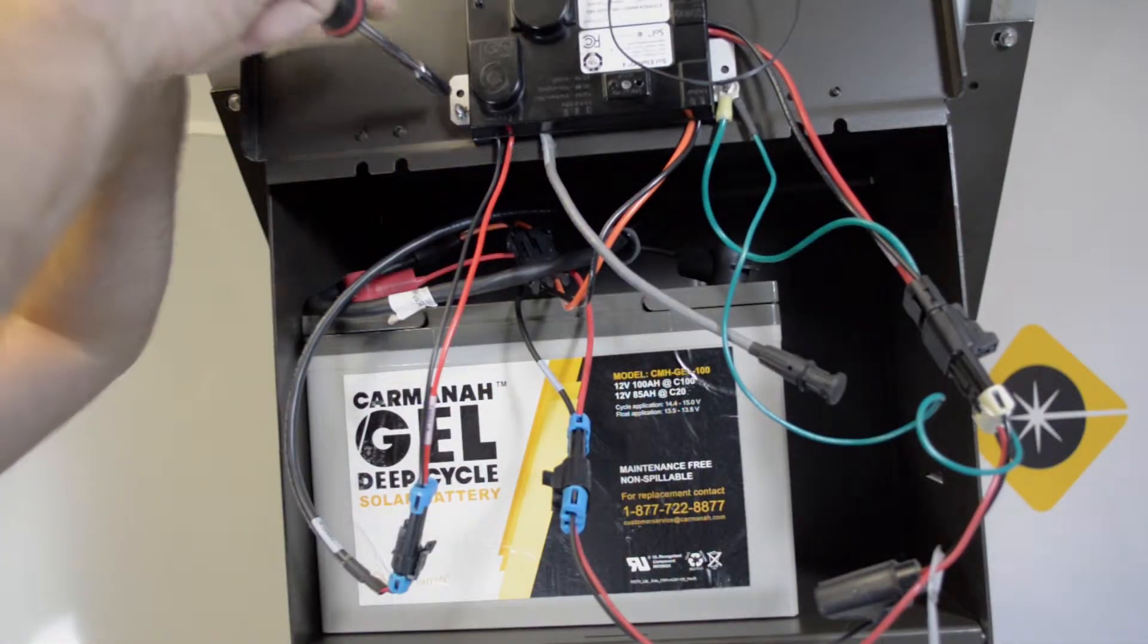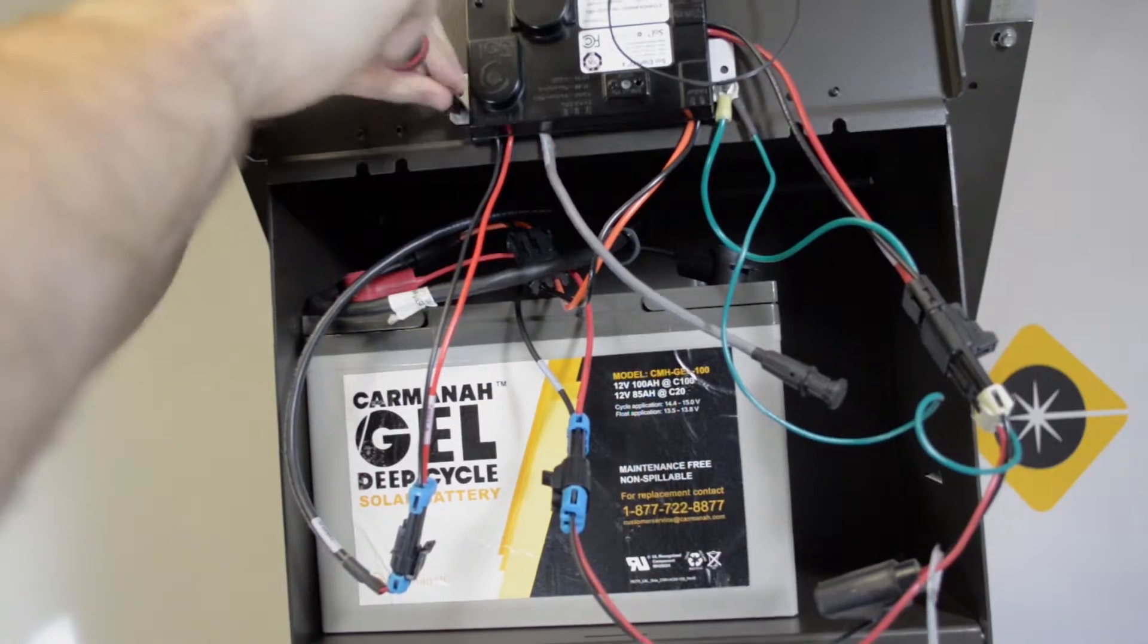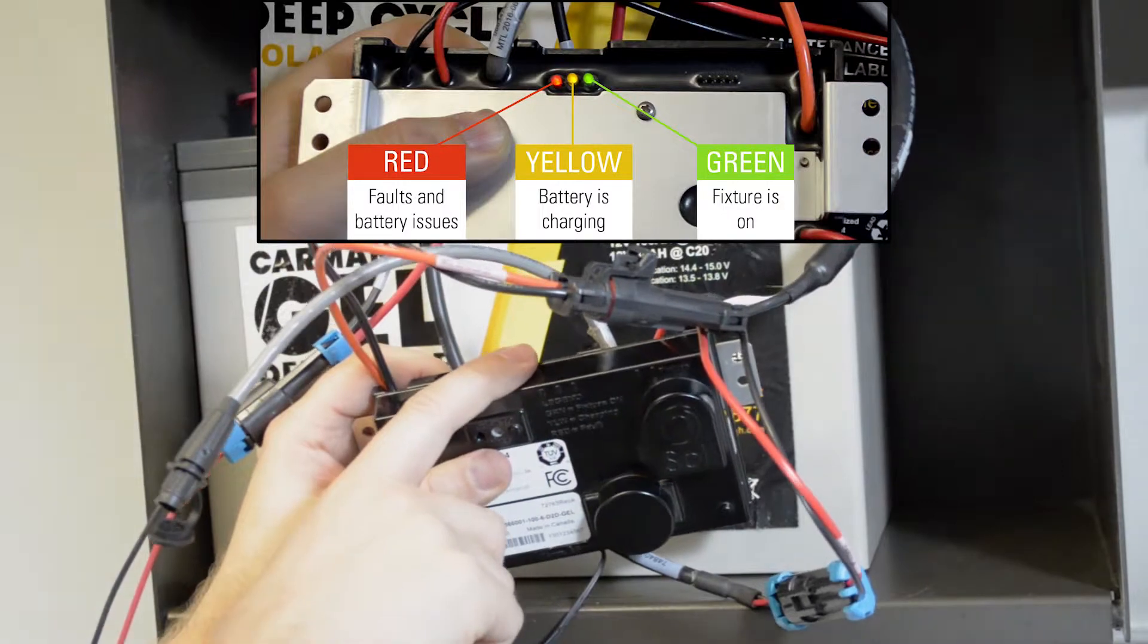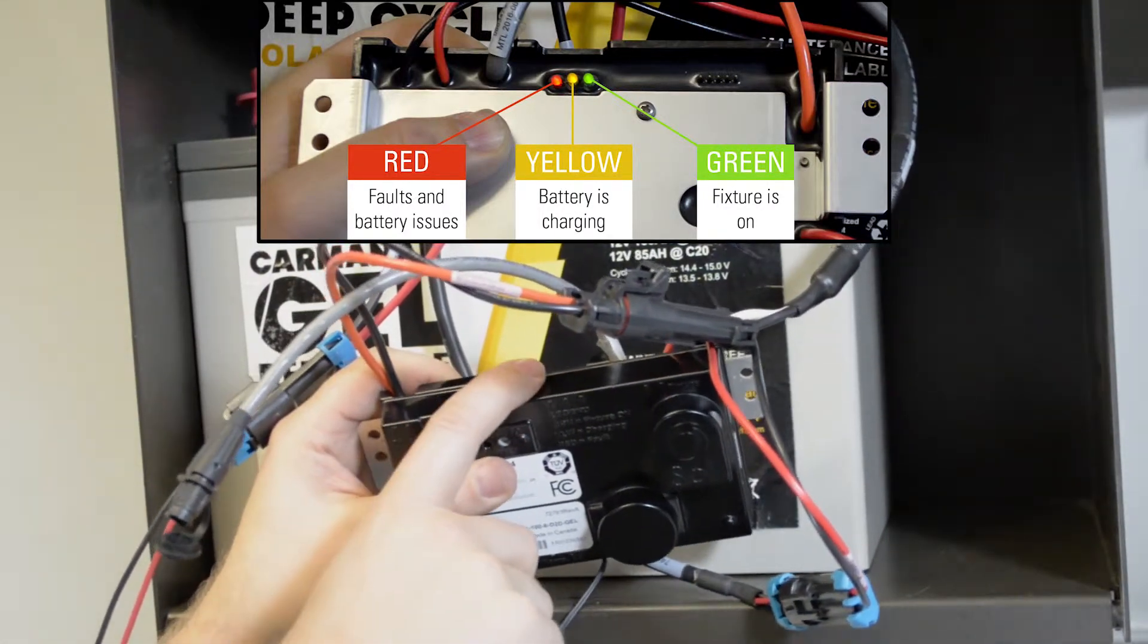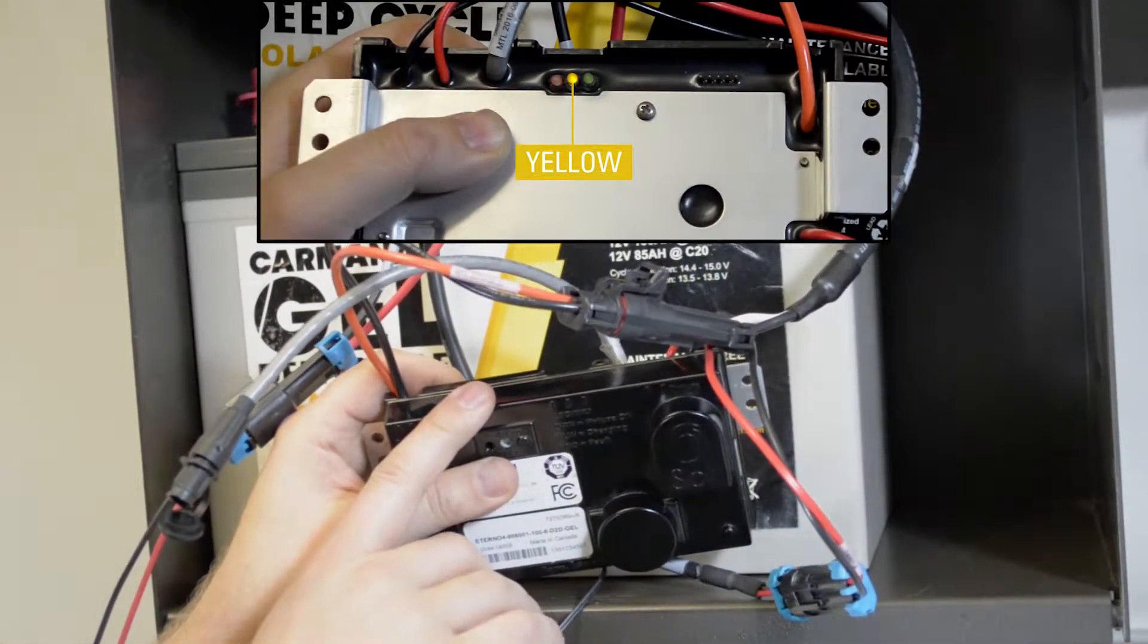Sometimes it's easier to remove the EMS to see them better before continuing with the troubleshooting. Use a quarter inch nut driver to remove the bolts securing the EMS. There are three indicator lights on the back of the EMS. Green represents the fixture, yellow represents charging, and red represents faults or issues with the battery.